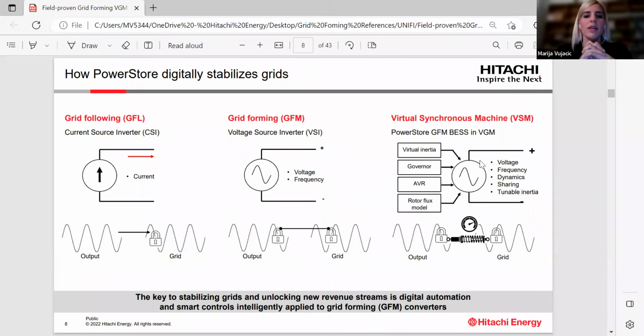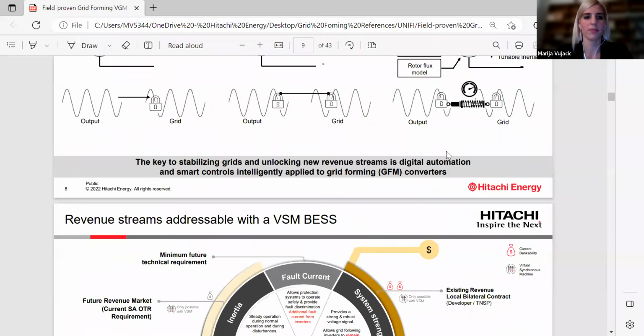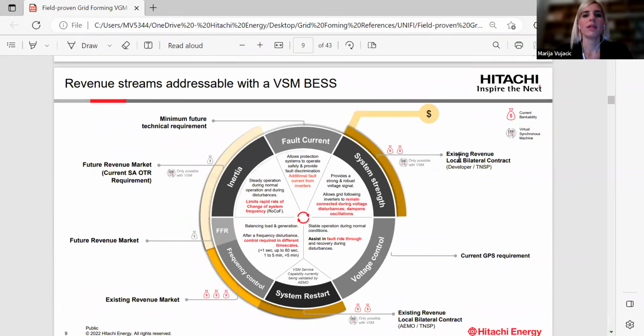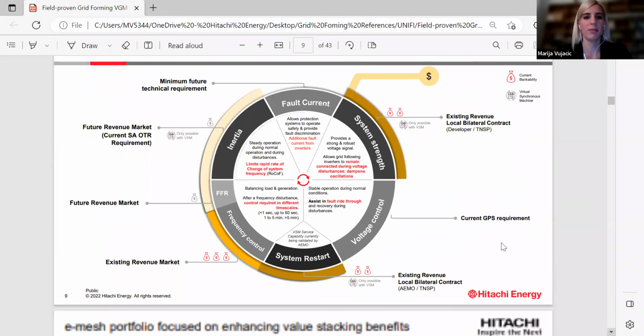It becomes important. So really the key to stabilizing grids and unlocking new revenue streams is digital automation as well as smart controls which are applied to grid forming converters. Ultimately, the idea is not only to replicate the capability of synchronous generators, but also to see how we can configure this algorithm to provide, if possible, even more services than a synchronous generator can do today. So we have proven that all these services can be provided by battery energy storage system, but the question is really, are they generating value to the customers? In the sense, are they all monetized today?